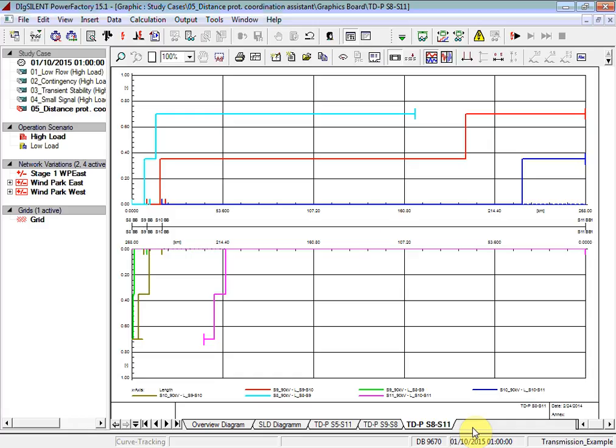Focusing on the reverse direction again, you can see that there is a problem. You can see that the zone 2 and 3 reach of the relay at substation 11 does not extend the full length of the line. This problem is caused because of the mismatch between the lengths of the first line and the second two lines. The first line is much longer than the second two lines. This causes a problem when using this particular zone calculation method.